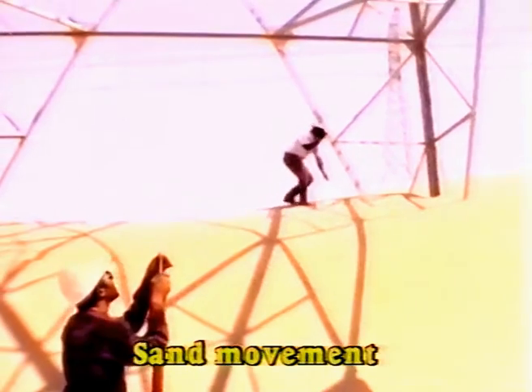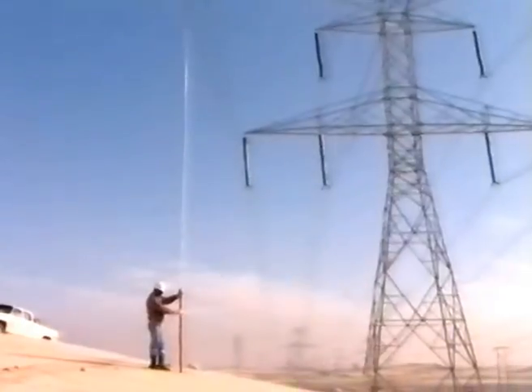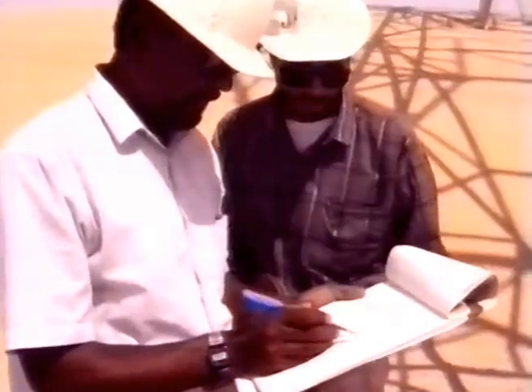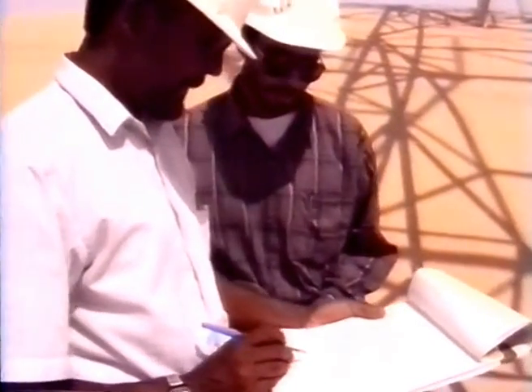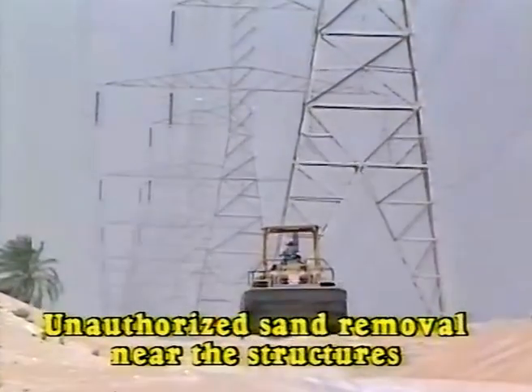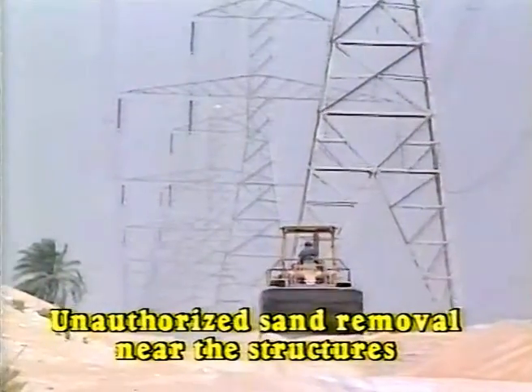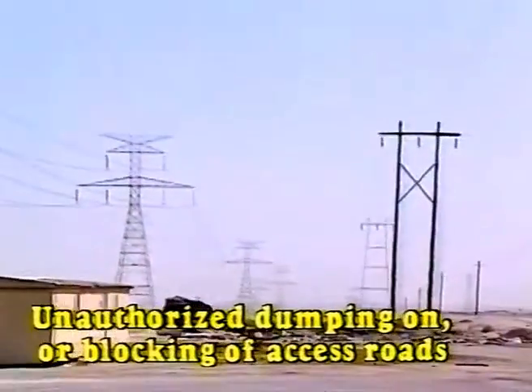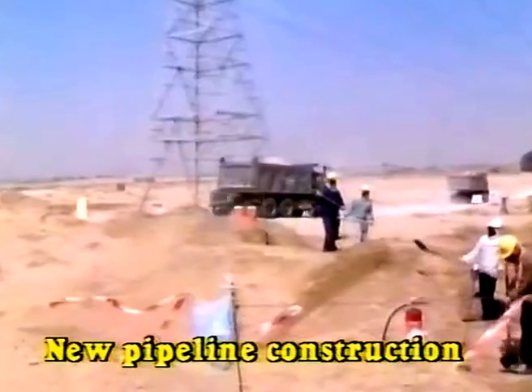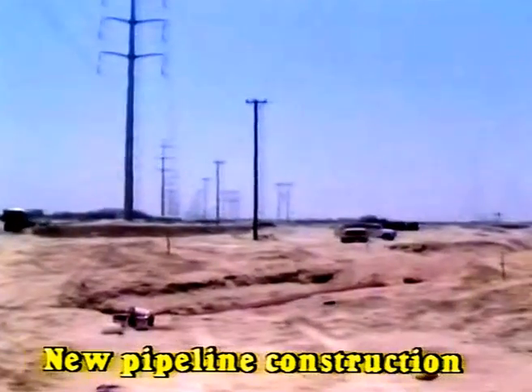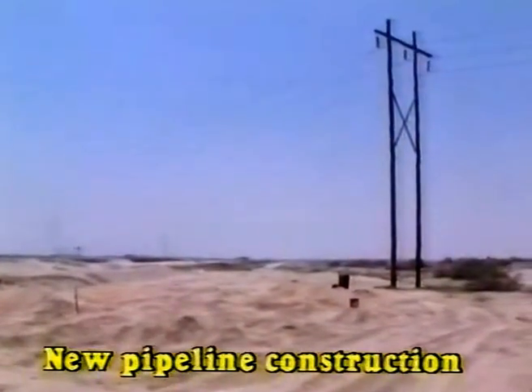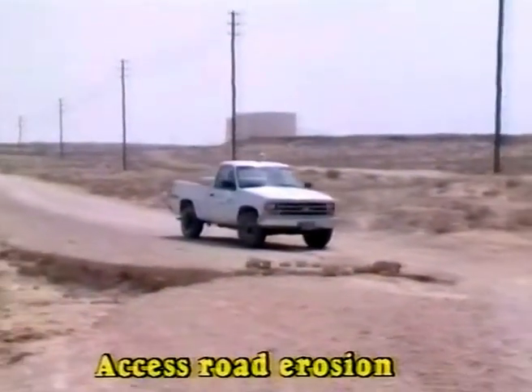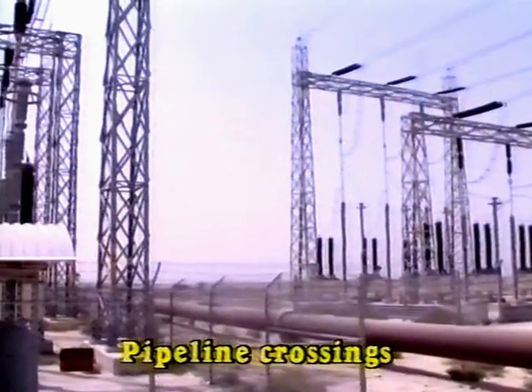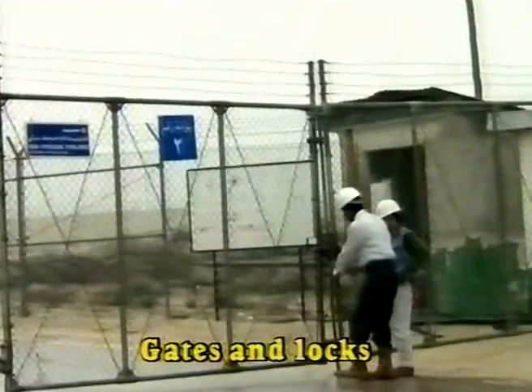Sand movement. It is important to check the mid-span ground clearances by using the teleheight meter or telescoping measuring stick. Make sure to note down your measurement readings and sketches on the report form. Unauthorized sand removal near the structures. Unauthorized dumping on or blocking of access roads. New pipeline construction near or under transmission lines. Indicate measurements to line from new pipeline. Access road erosion. Pipeline crossings. Gates and locks.